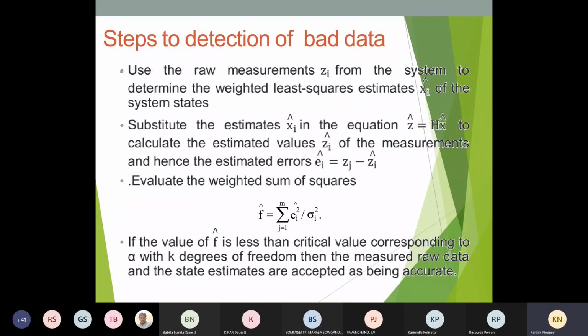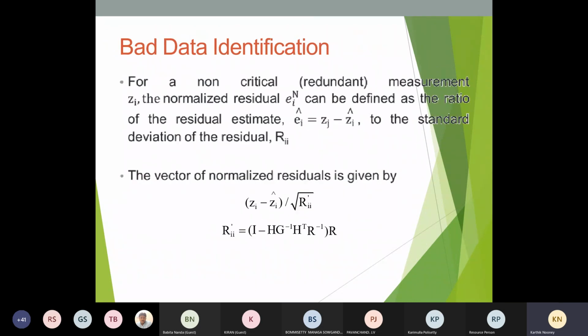If that particular value is less than our critical value corresponding to alpha with k degrees of freedom, which is assumed by the chi-square distribution, a table is there, I have not mentioned it here. With that table, we will fix the tolerance. If it is less than that tolerance, your data is not bad data. Whatever the error, if it is more than this tolerance value, then you can identify that the measurement in that part of the network is bad data.